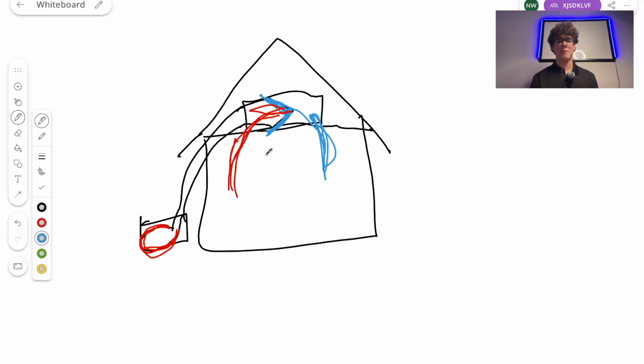A heat pump basically adds what's called a reversing valve that allows us to then have cold refrigerant out here, which allows us to absorb heat from the outside air. We'll talk about that later. And then we can bring that heat inside using refrigerant, and we can actually have a hot coil and turn our cold air in the home into warm air. Basically, the heat pump in heating mode allows us to heat using the same system, if that makes sense.